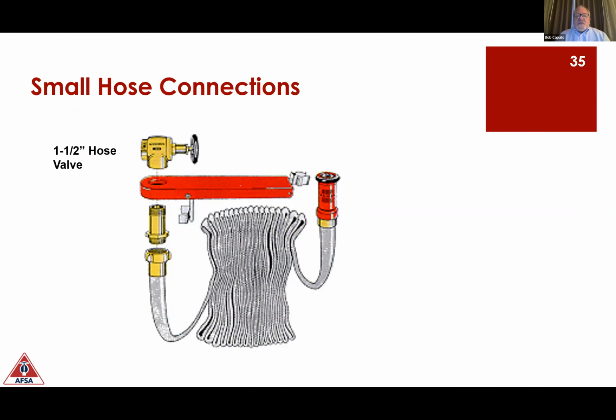In these warehouses, you'll see these small hose connections that are connected to the fire sprinkler system. NFPA 13 no longer requires these, and if you have them in the building, the local fire authority can allow them to be removed. First responders will not use fire hose that is owned by the building, not owned by the fire department. Predominantly, that's because they can't trust these hoses. They're of low quality. They're not lined or jacketed. They're just basically a cotton hose. They're not maintained. And unless you have a charged hose that has been tested in your hand, you're not going to go into a burning building to save boxes. They'll go into a burning building to save life, but not material.